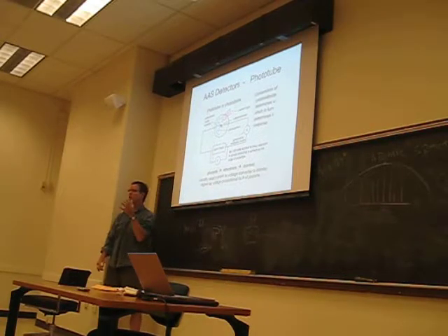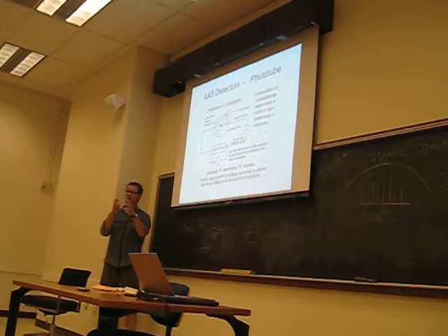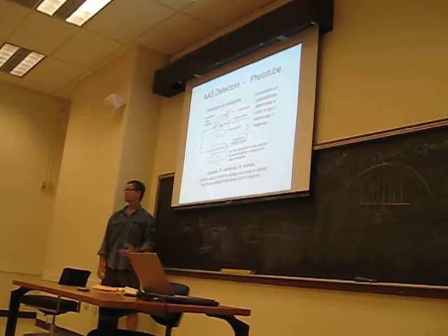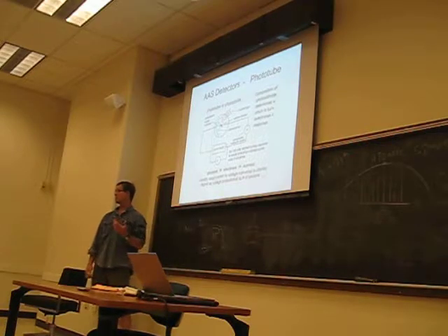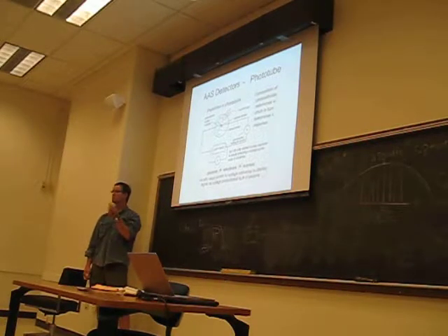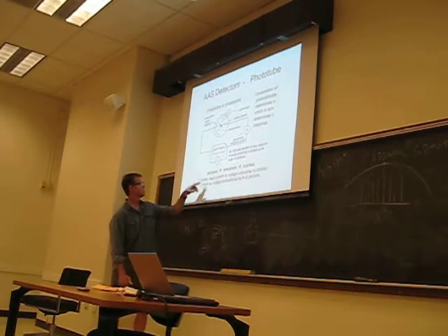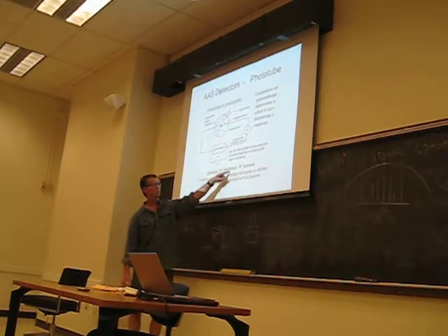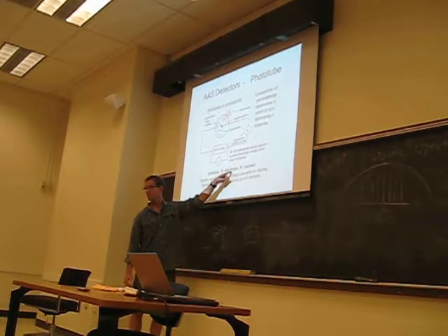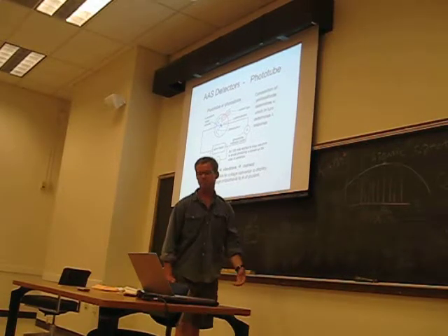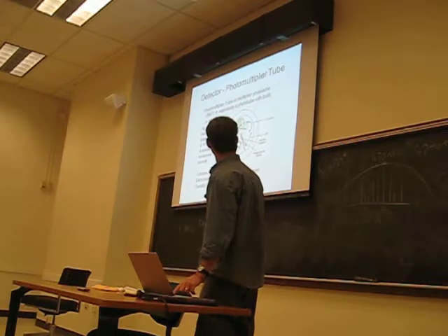So it's an analog version of converting photon intensity to current. And that's what a readout is. Essentially, you're getting a relative current in terms of absorption, in relative absorbance units. That's the current on that detector. So you're taking photons, freeing up electrons that are kicked off that photo sensor coating surface, and generating electrical current as a result of that.